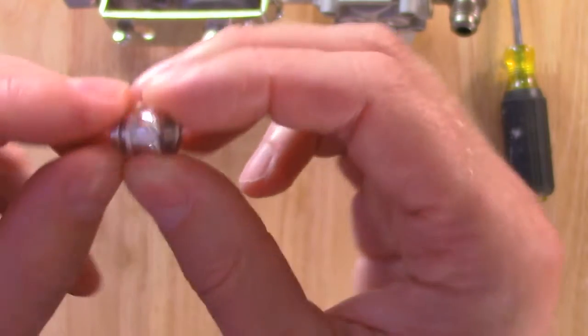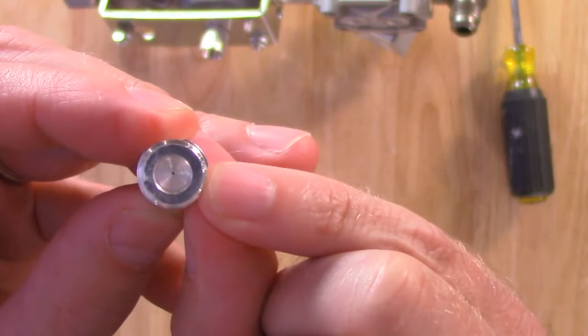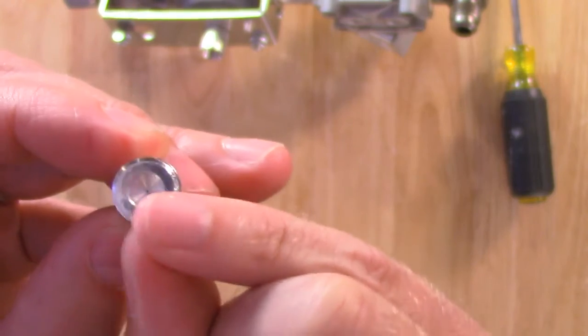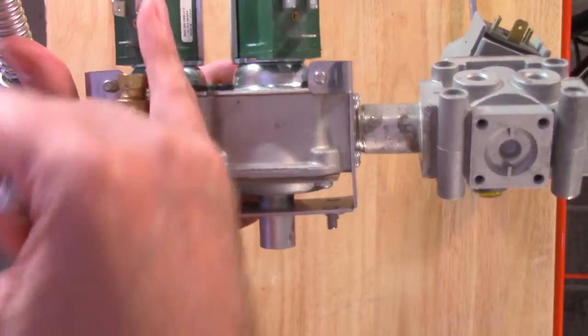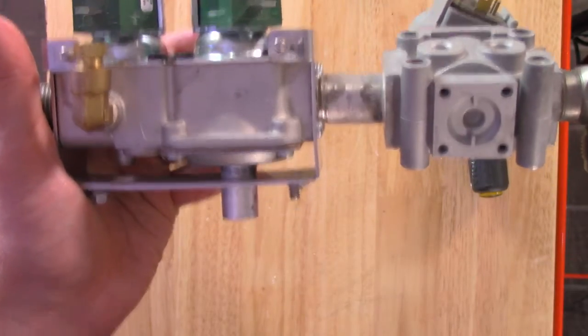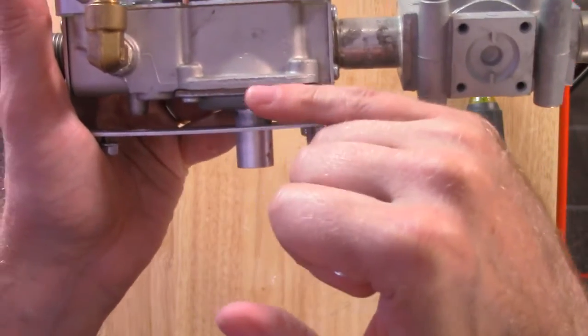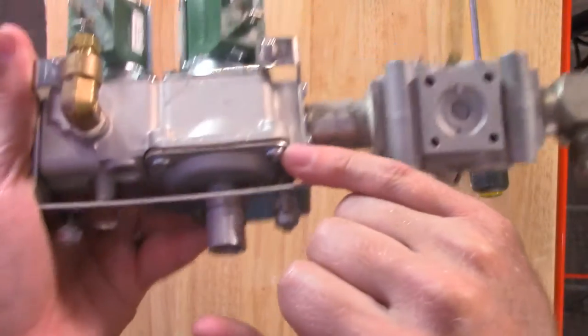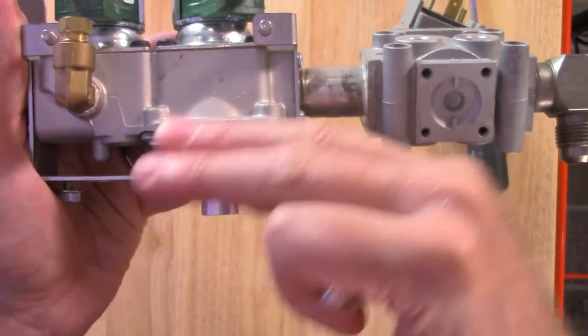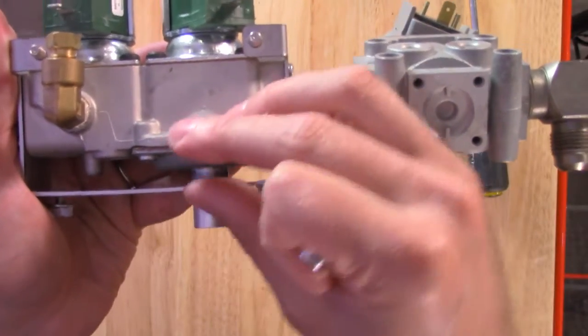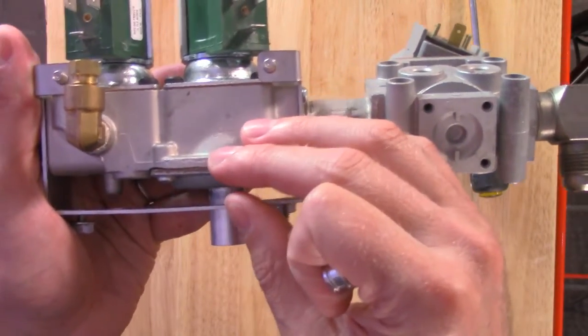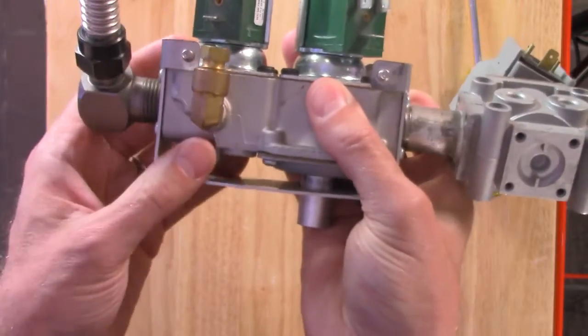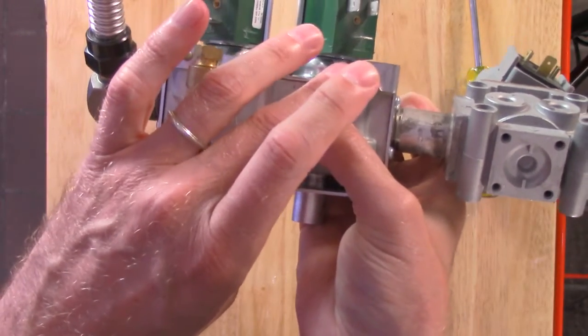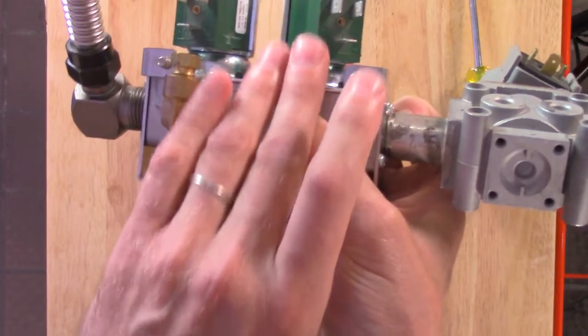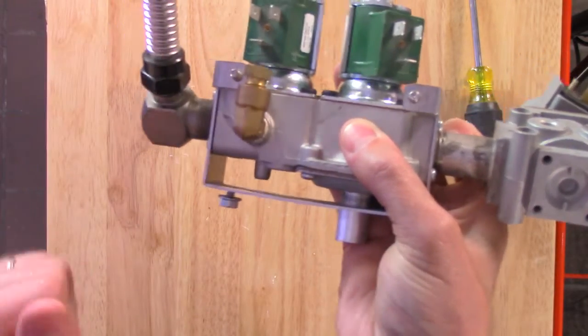So this goes horizontal, and then you have this little itty bitty pinhole down in here that is going to be going down in. And how that works, and why that's an issue if this gets clogged: this is for my main burn, and this is for my pilot. If this gets clogged, then you have this diaphragm in here. You can see the diaphragm kind of going across. If it's not allowed to equalize the pressure as it opens and closes, it could stick, and then it's not going to allow the main gas to go out, or your pilot could end up slowly fading away, or you just don't get the main burn, allowing the gas to flow on out.